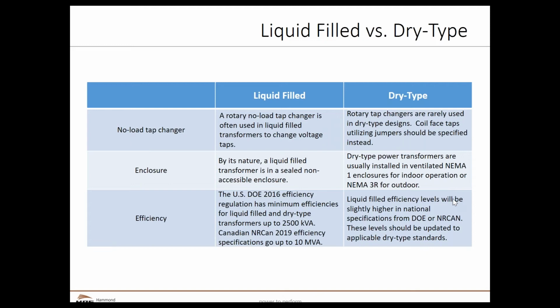Okay, and we sometimes have people say, well, I still want the no load tap changer. Well, in order for us to put contactors in that can do that becomes a very complex and expensive means to do for a dry type transformer. Again, we would just say change the taps. By its nature, liquid filled transformers are sealed in a non-accessible, non-ventilated enclosure. Dry type transformers, by their very nature, are ventilated. And again, those ventilation holes provide us with some concerns that the transformer is accessible to the general public.